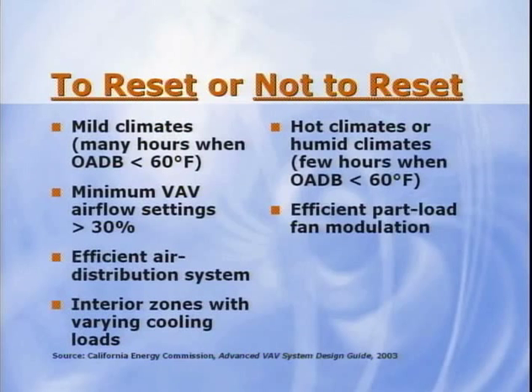Systems with efficient part load fan modulation. Using a VFD on the supply fan and a fan pressure optimization control strategy often make it more advantageous to reduce supply airflow and save fan energy rather than increase airflow and save compressor energy.